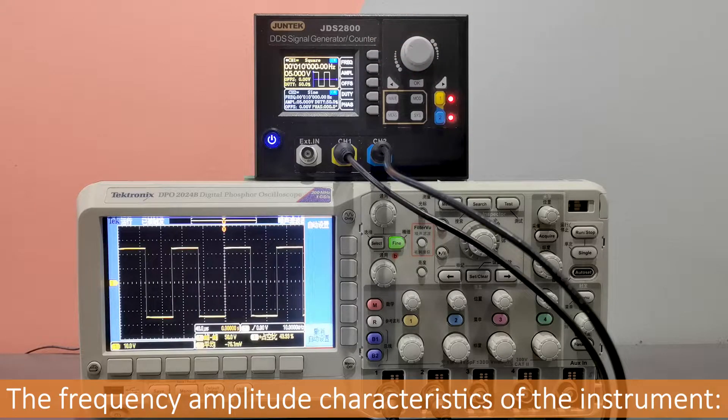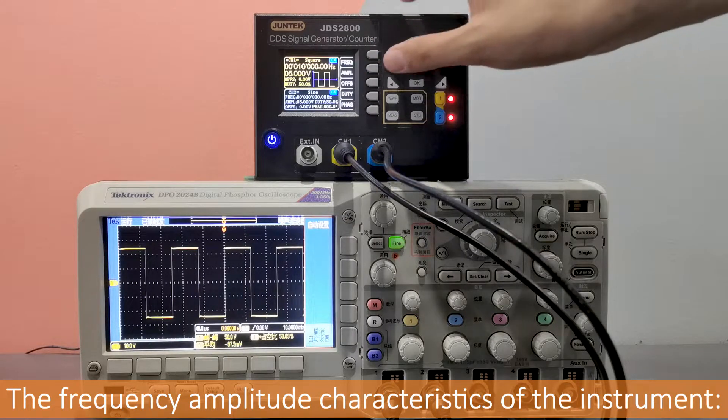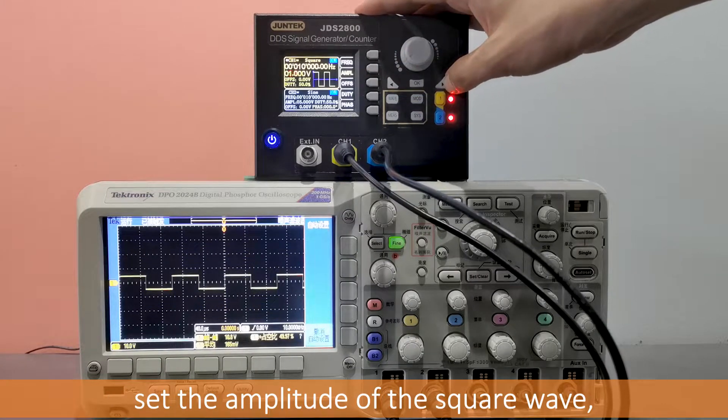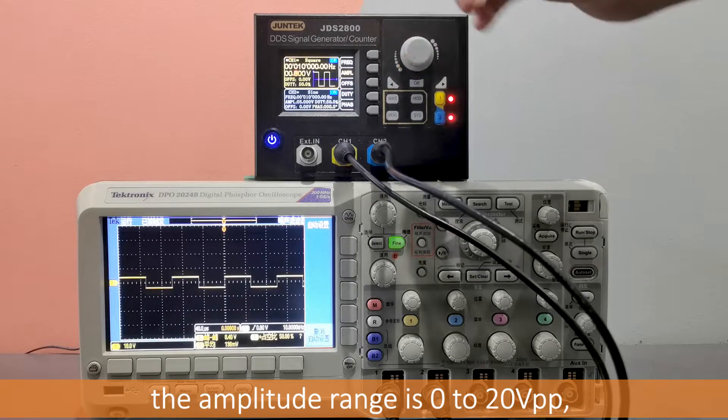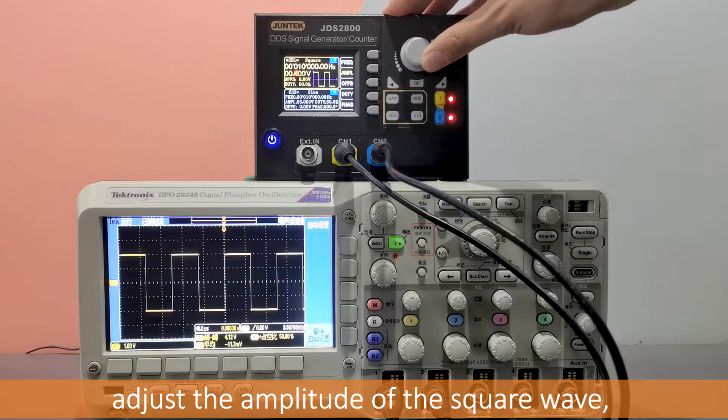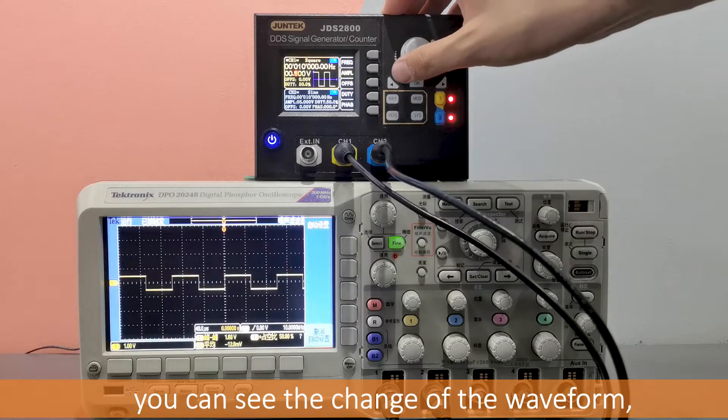The frequency amplitude characteristics of the instrument. First, switch the waveform to square wave, set the amplitude of the square wave. The amplitude range is 0 to 20 VPP. Adjust the amplitude of the square wave, you can see the change of the waveform.